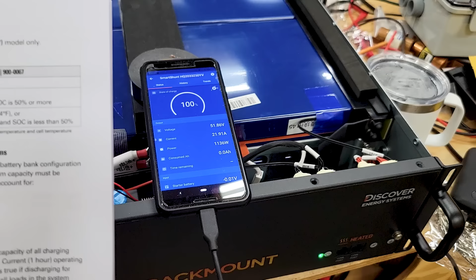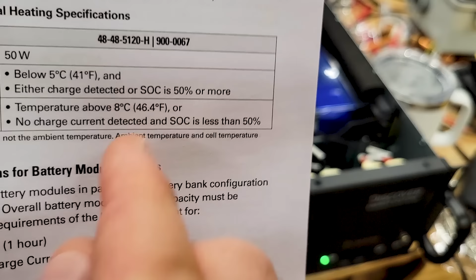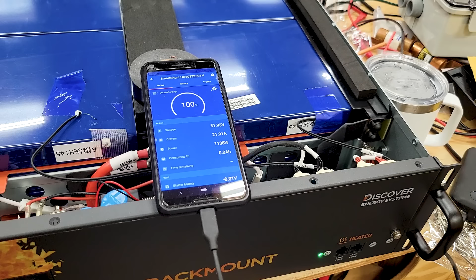Now the battery management system sees that we are above freezing and safe to charge the batteries. The manual actually says above 8 degrees Celsius, or 46.4 Fahrenheit, and then it turns off the heating. So now the heating system is off and we're charging the cells at full blast.